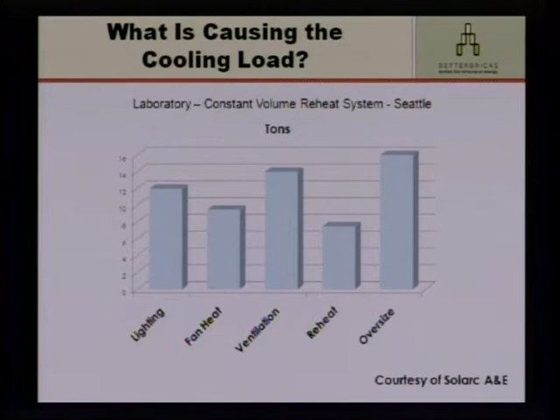Fan heat is interesting because it's essentially the energy used by the system that distributes the cooling. So part of the cooling load is cooling the system that's making the cooling. The bigger that system is, the more you'll have in this category. Reheat isn't as big an issue, primarily because you're not extra cooling. What you're doing is cooling as close as you can and then reheating what you don't need, which is why it's not as big an issue as it is on the heating side.